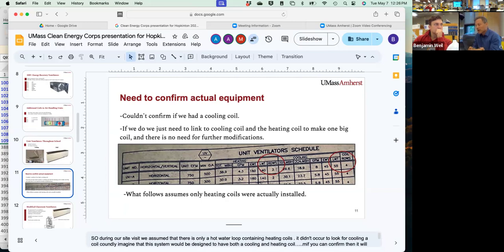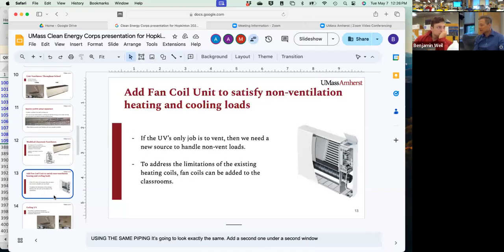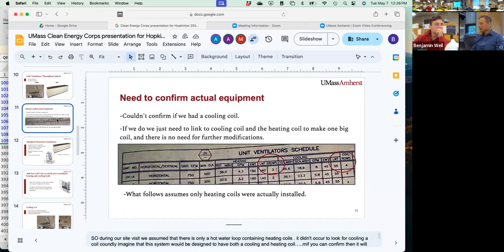And if you've got a cooling coil, you probably have condensate management, right? Some sort of drip tray. And then you have to figure out, well, how do we get the condensate out? And it might be as simple as put a hole in the wall and send a tube outside, through each of these wall unit ventilators. If that's the case, then you don't need to add any fan coil units. And we're talking about hundreds of dollars, not thousands of dollars per classroom. And you've got cooling. And you've got the ability to run 105-degree water. So if that's the case, that should be part of your capital budget because all of a sudden you're getting cooling everywhere.